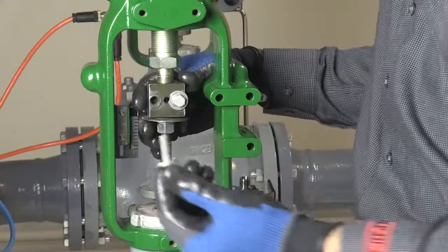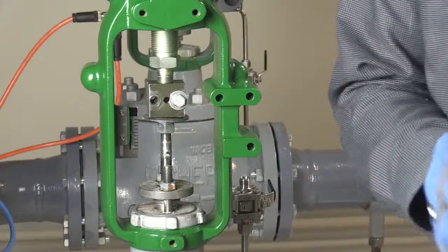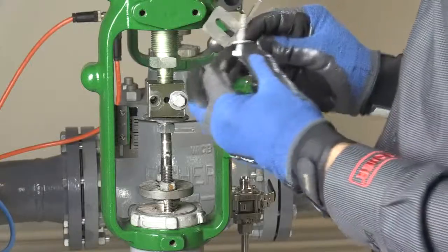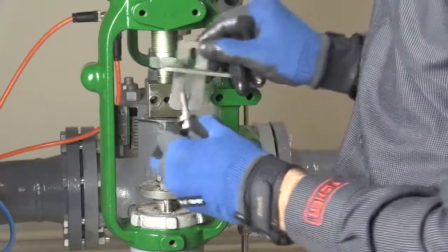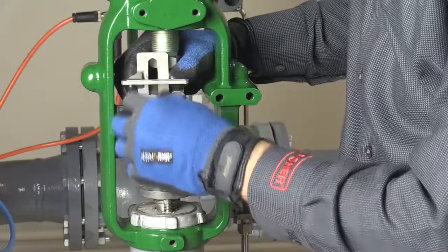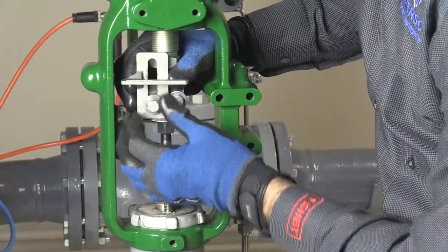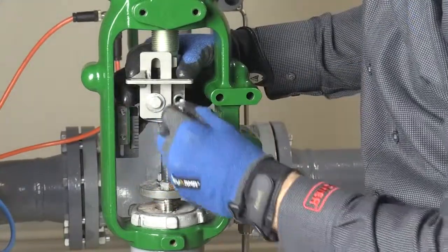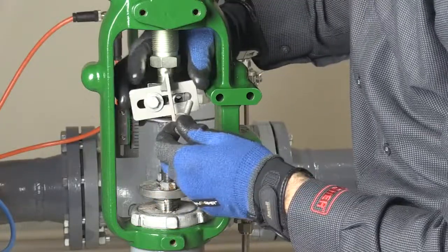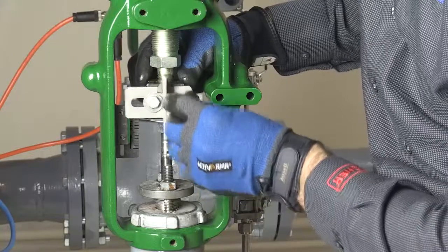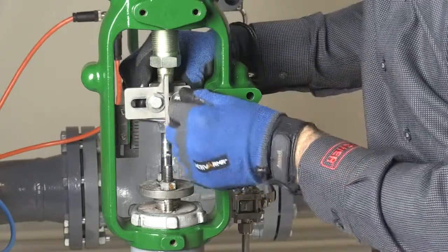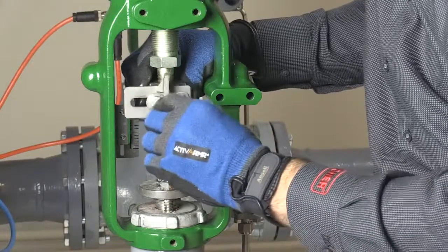To attach the connector arm, first remove one of the two bolts from the coupling block. Then, install the bolt through the slot in the connecting arm and tighten. Repeat this process with the other bolt. Leave the bolts loose because we'll fine-tune the alignment here shortly.